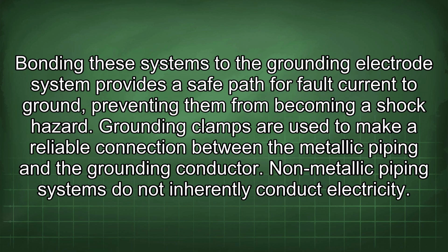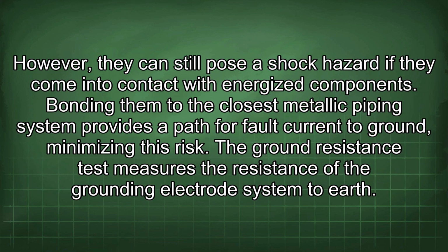Grounding clamps are used to make a reliable connection between the metallic piping and the grounding conductor. Non-metallic piping systems do not inherently conduct electricity. However, they can still pose a shock hazard if they come into contact with energized components. Bonding them to the closest metallic piping system provides a path for fault current to ground, minimizing this risk.